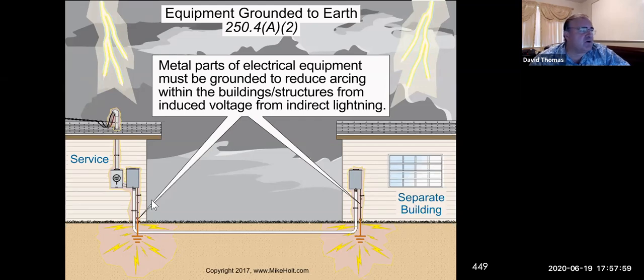Induced voltage can also come from within our own wires. The electrons flowing through a wire can induce effects in the metal objects, the ferrous material, and excite the electrons to move in the conduit. That's why our conduits have to be properly grounded, so we discharge any of those unwanted movements of electrons. If we don't do that, we create chokes where the electrons will not be able to flow, because as you remember, it's basically a big inductor.